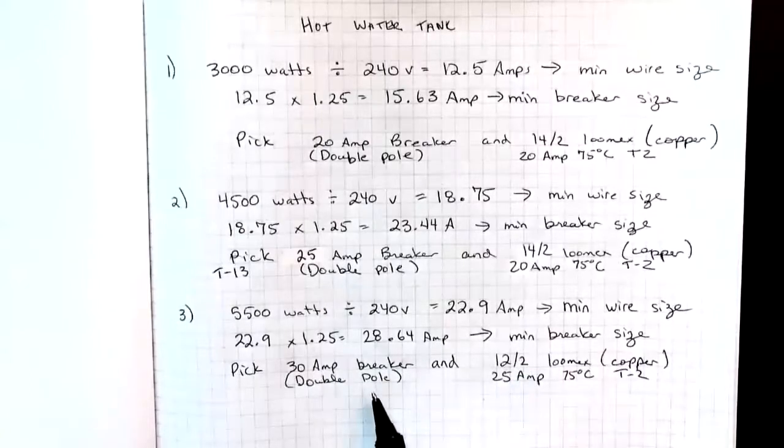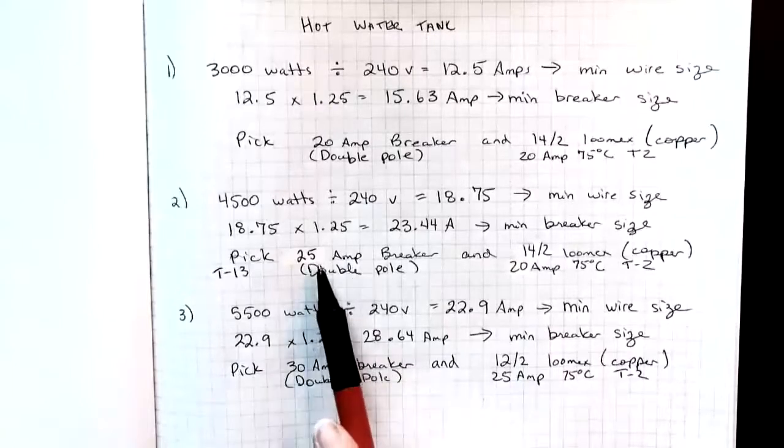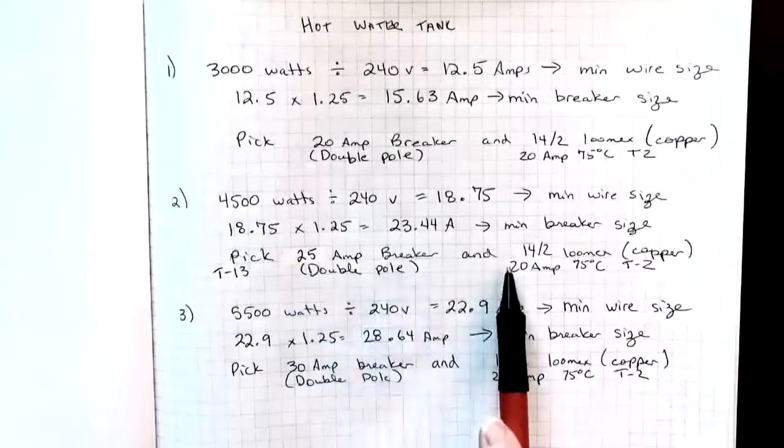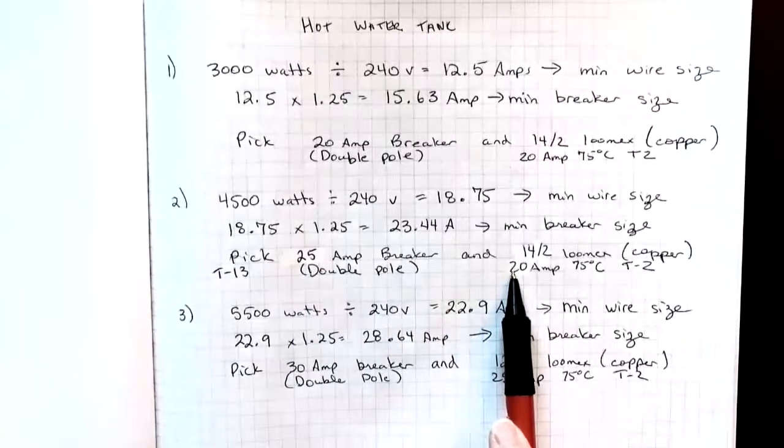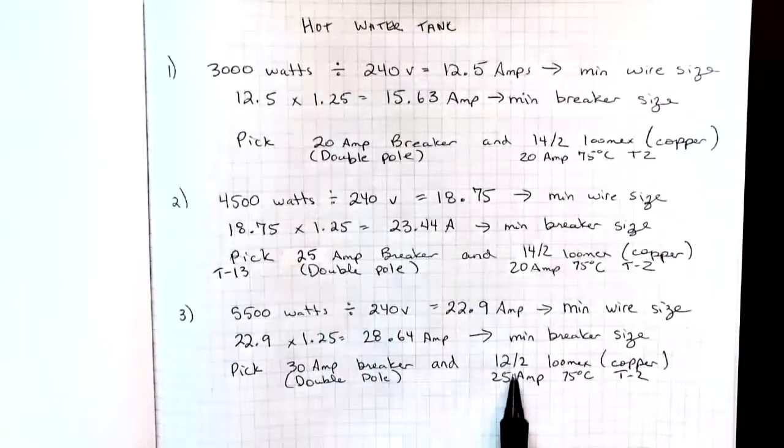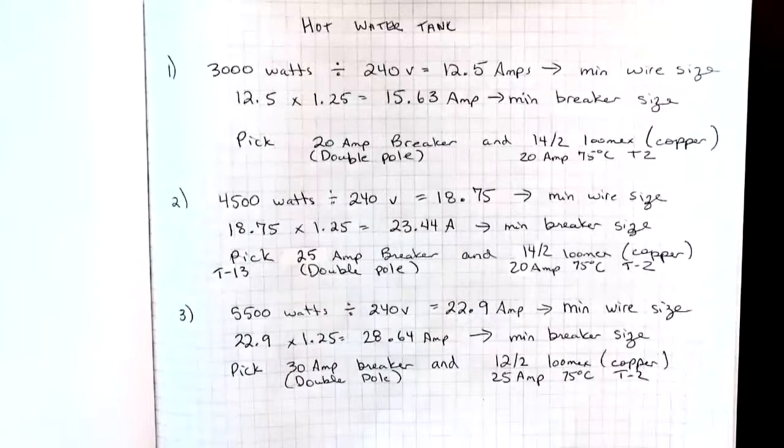Notice that in all of these, in these last two cases, we have a breaker that's rated for higher than the ampacity of the wire. And that's fine according to the rules that we saw in the previous video.